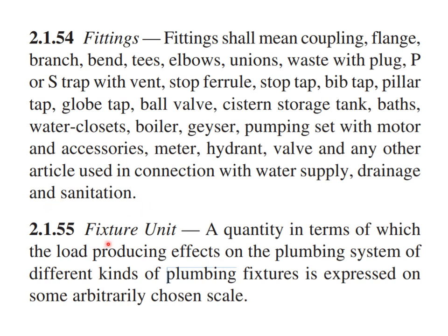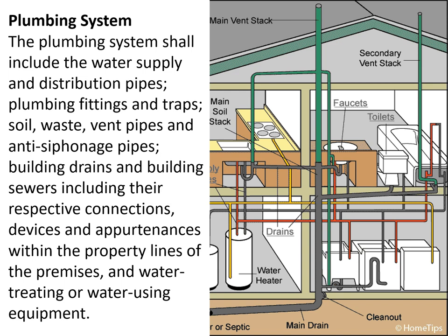Whereas the fixture unit is a quantity in terms of which the load-producing effect on the plumbing system of different kinds of plumbing fixtures is expressed on some arbitrarily chosen scale. For example, the spout of a bathtub is considered as a fitting whereas its fixture unit is equivalent to 3, so far as water consumption is concerned by that particular fitting.